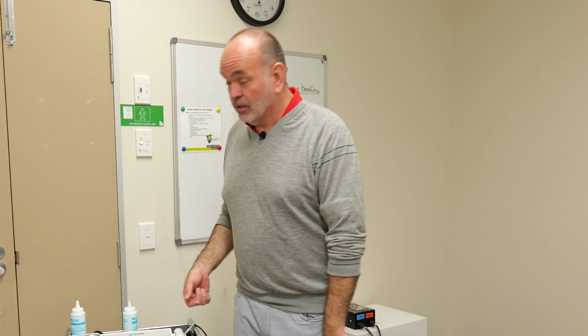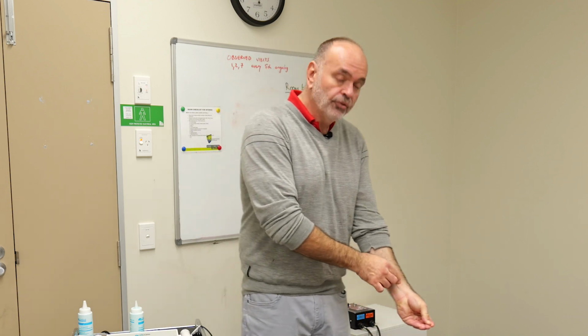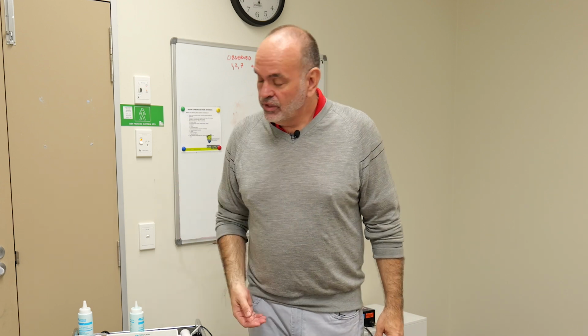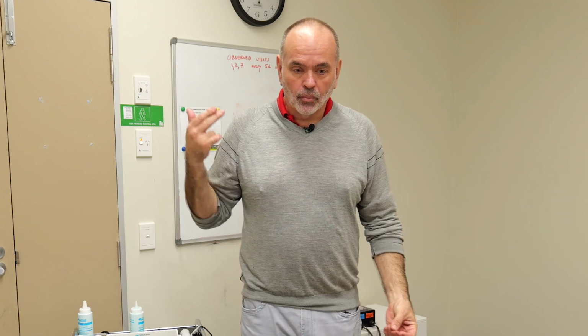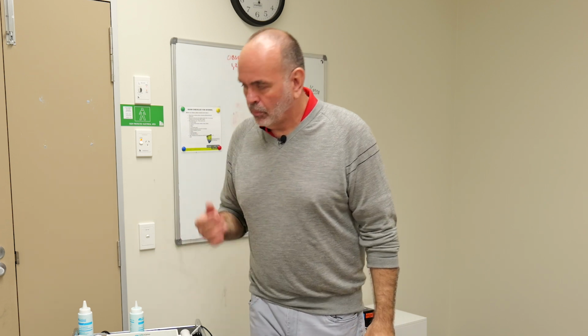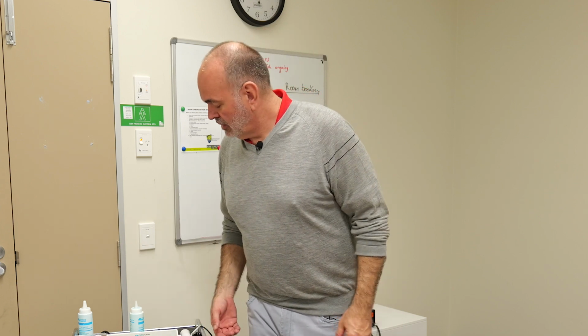So in terms of setting up the machine, for deep tissues, for example, a muscle that has more thickness to it, we're going to use a lower frequency, meaning 1 megahertz, and we're probably going to need more power, more energy to deliver a therapeutic dose to those tissues. Whereas if we have something superficial, like some of the tendons that go to your wrist or to your hand, they're right near the surface. They're also small structures, so we don't need as much energy. And we can use, number one, a higher frequency and less energy. And when we talk about energy in ultrasound, we measure it in watts per centimeter squared, so energy per unit area, right?